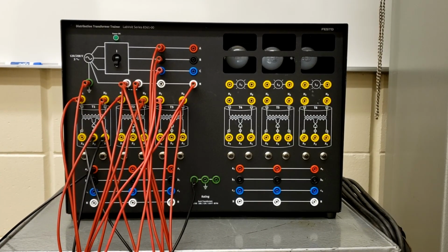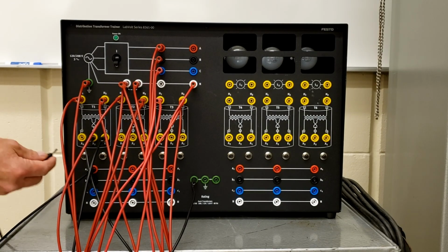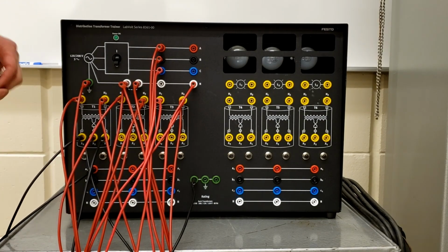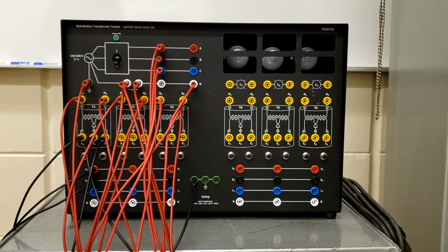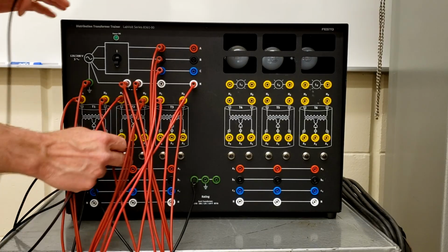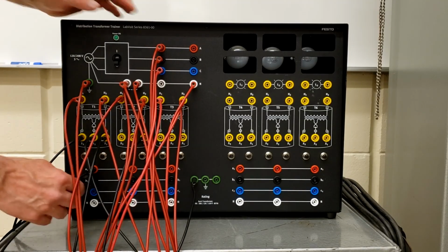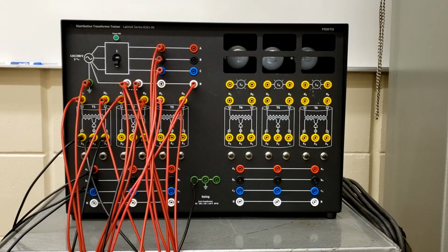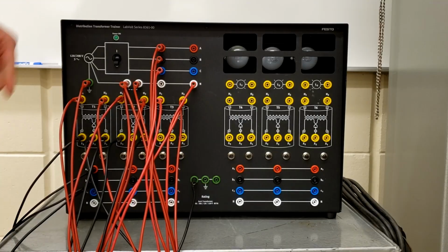Okay, then we've got X3 should be going to B. It is. So X3 is feeding the B phase. Okay, then we should have X1 of the next transformer, transformer 2, going to B. Yes, it does. So X1 is feeding the B phase. Then that X3 of that guy should be going to the C phase. Excellent. So X3 feeds the C phase.